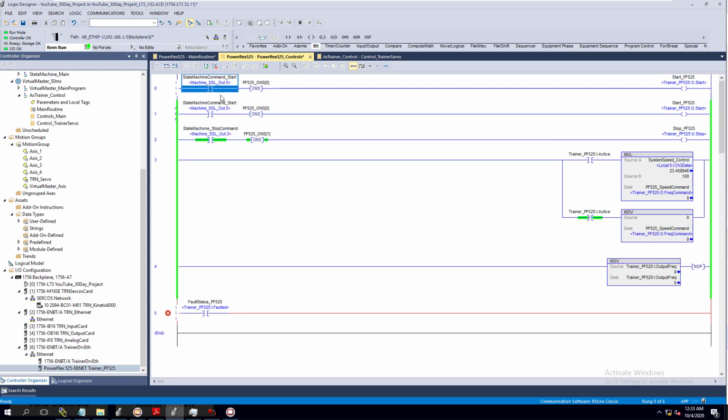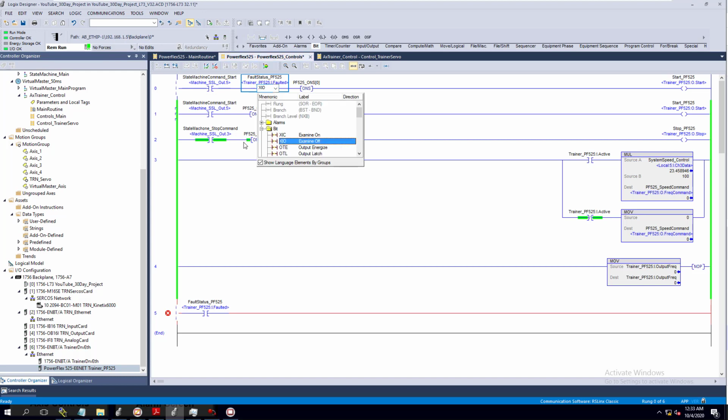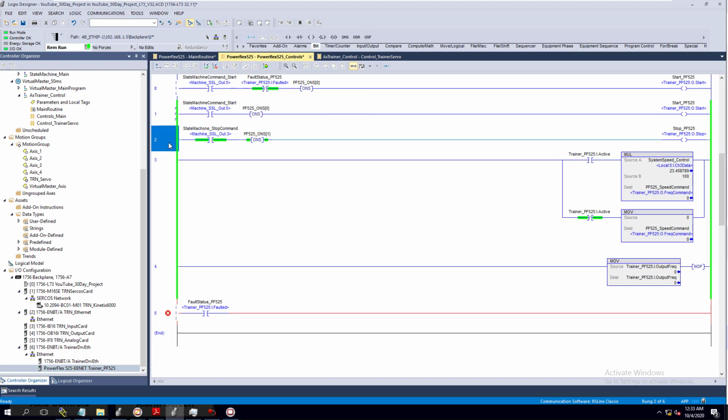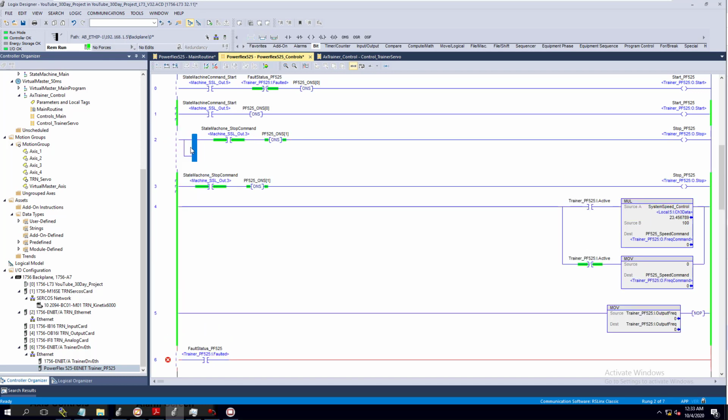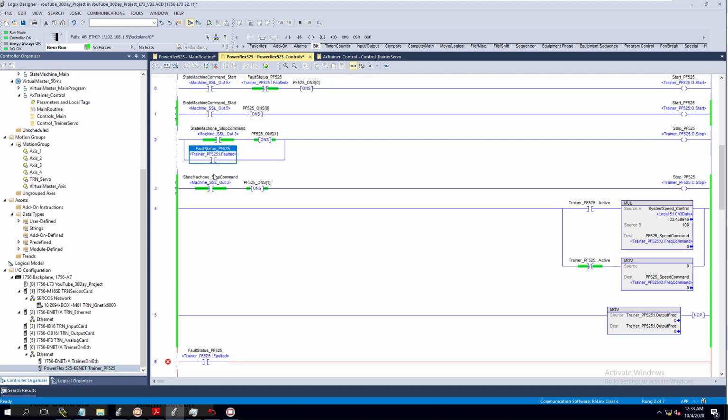So let's come up here and throw that in there and throw this in here, and just make sure, for the sake of control wise, what you're doing is you want to make sure you throw in another command to verify that the stop has happened. And the reason I say this is because when a drive logic is going through the process, right, it sometimes will latch itself into a run, or into a state where it's running, or it tries to run and it never does run. Then you try to start it again, it never does actually run because it's still stuck in that last state. So the best way to do this is to always default back to a stop on a negative outcome, right? Which would basically be a fault, right?